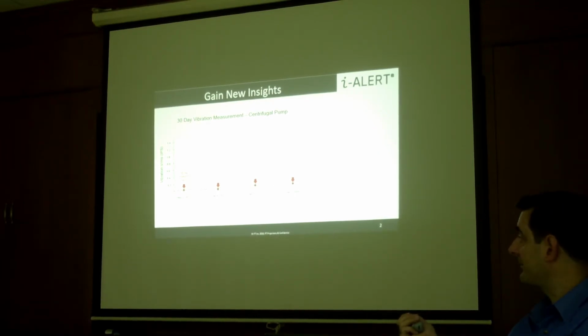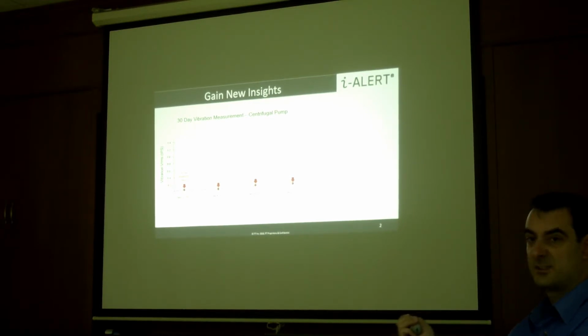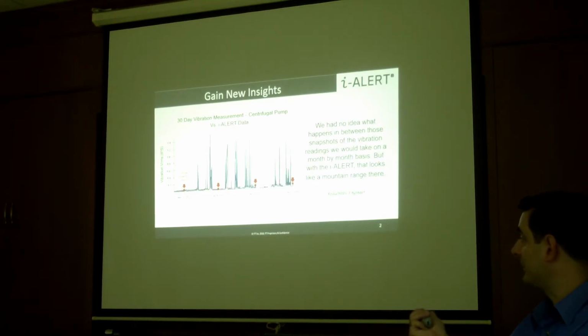But here we have a customer who measured vibration every 2 weeks. Just over 2 weeks. They had a pump failure, but from their history, this is inch per second. They did not have many, the vibration was very low. But they had an iAlert on the pump and they were not using it, but it was there. And that was the result.